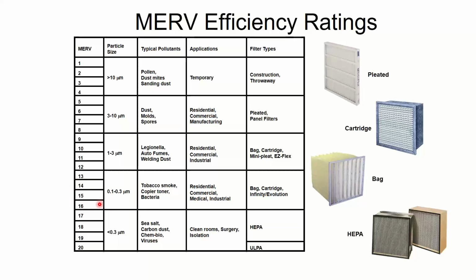If you look at any of the recommendations from ASHRAE that came out after COVID, one of the recommendations was to get your system, it was weirdly worded too, up to MERV 14 level, right? Because that was going to catch an appreciable percentage of the SARS-CoV-2 virus, assuming you get the virus to the filter, which is another debate.